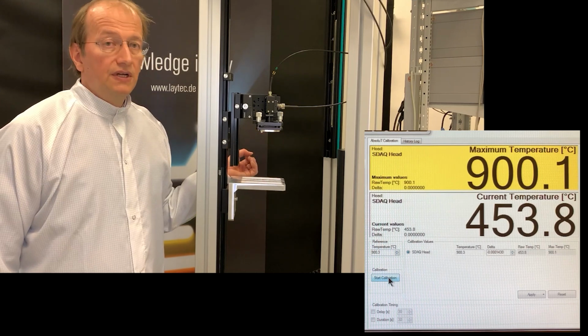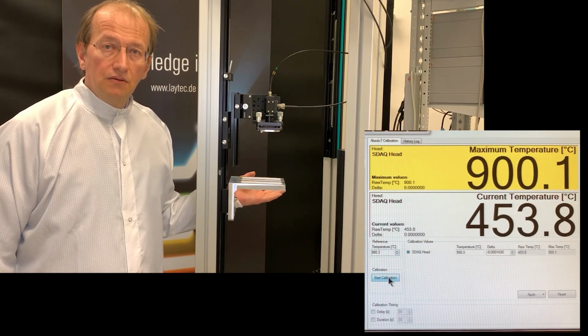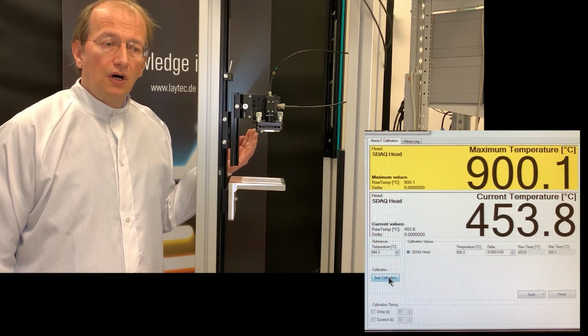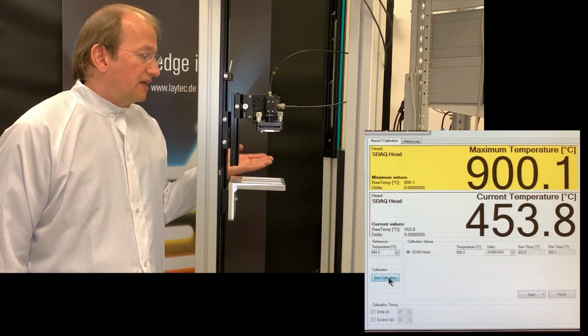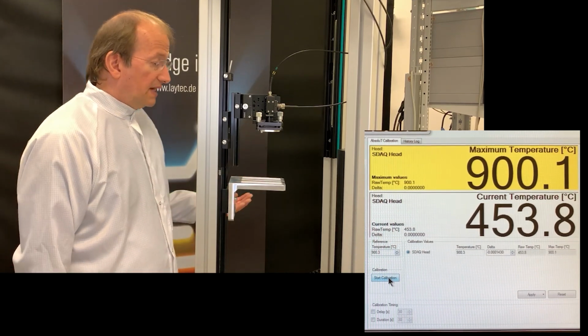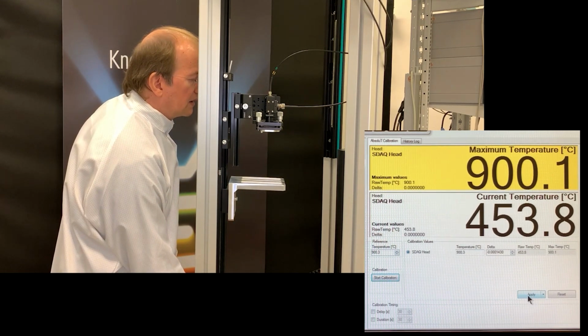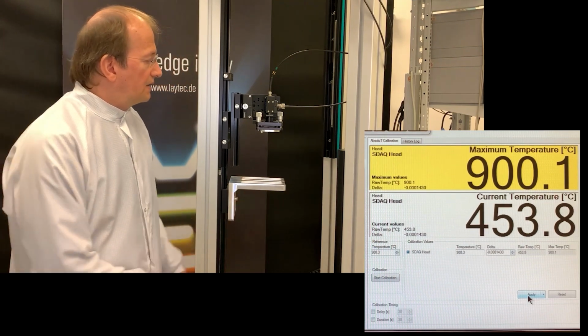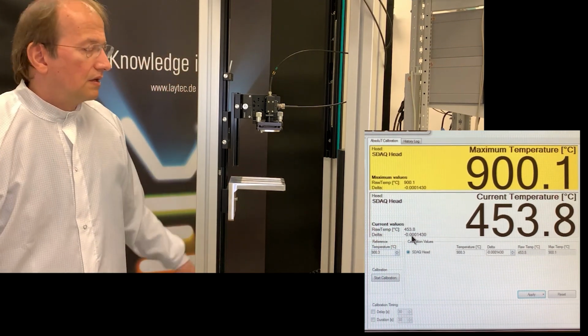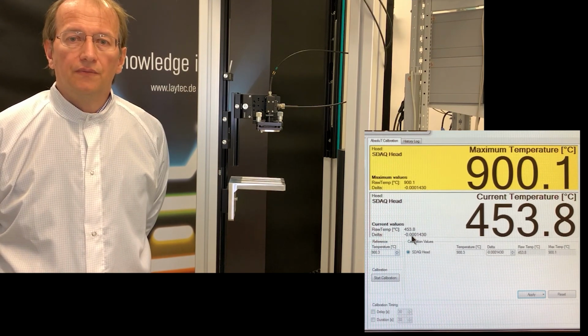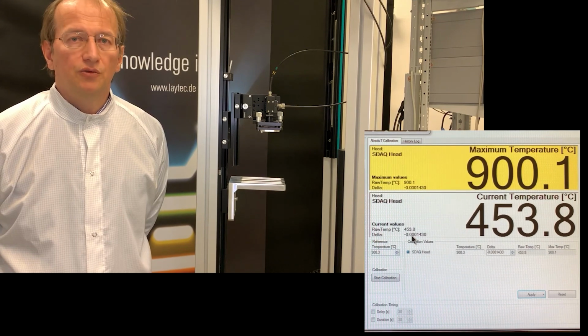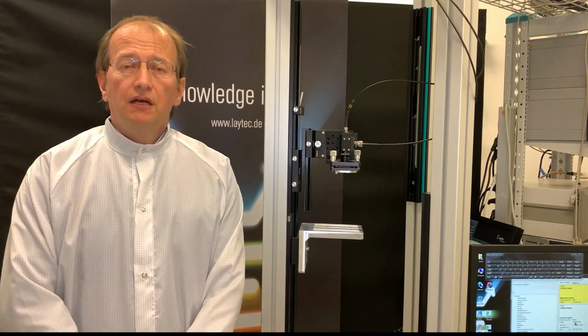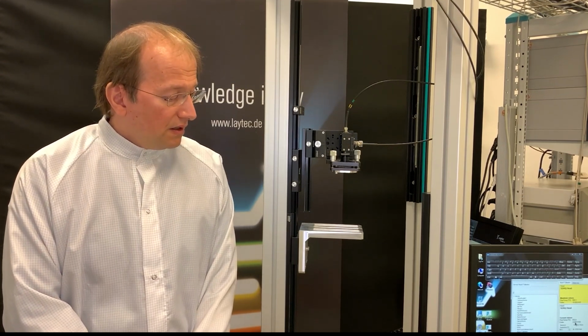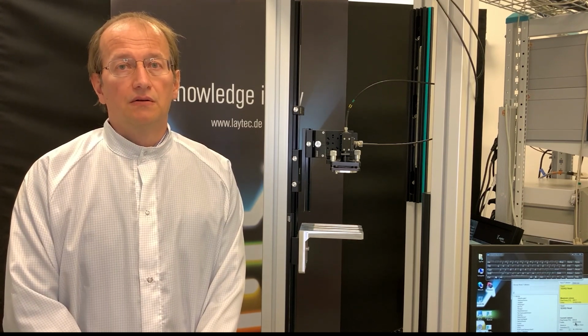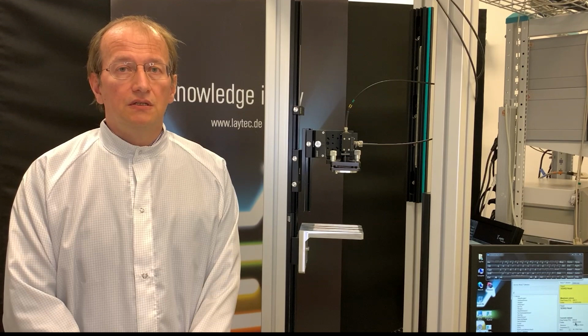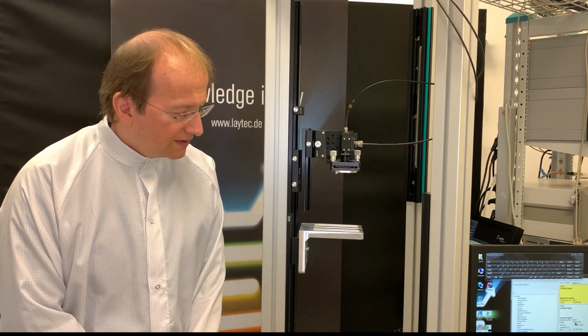Use this as a reference measurement, and automatically it will not apply the correction function. If this is the final approach and you are happy with the result, everything makes sense, then you can apply the value by pressing this apply button, and then the value, the correcting function, is submitted to the internal data holding place, and it will be automatically applied for the next measurement. That was basically the AbsoluT calibration. So with practice, after 3-4 tries, you are really comfortable in repeatedly getting the same consistent result. So thank you for your audience, and see us in the next part.